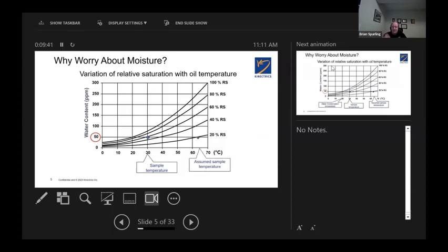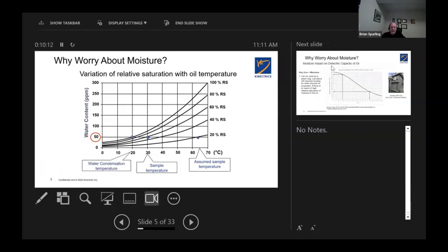If they had taken the sample, let's assume the sample temperature was somewhere up around 65 degrees C, and the laboratory has measured 50 parts per million, then the saturation of that water in oil is just under 20%. And that's the limit of saturation of moisture in the oil as defined in the IEEE and IEC standards for moisture content in the oil, 20%. So it's on the border, so to speak. If the sample was at 20 degrees C, it has probably rained already inside the transformer, because at that level, 50 parts per million at 20 degrees C is the water condensation temperature. It's reached 100% saturation. People say, well, how can this be ppm? We've been talking about it for years and years, and that's true.